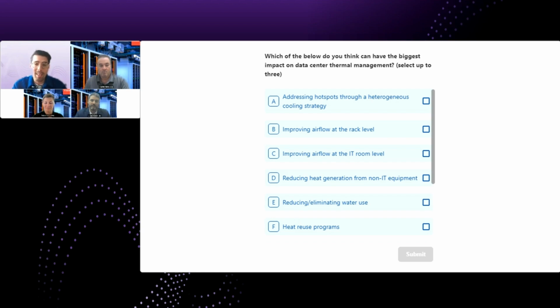This brings me back to the same report I read from the Singapore government. There's a very clear realization there: Singapore's PUE will never be as good as the PUE in the Nordics. And that's fine. So it's really more about finding an efficiency gain, improving the status quo. That should be the focus. So in how you think about PUE, it's not just about the world's best PUE, but what is the optimal PUE you can achieve, or how you can take steps to reduce your PUE. I think that's actually what's more important.